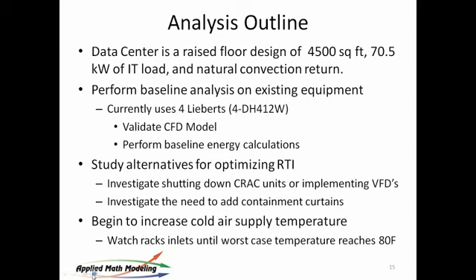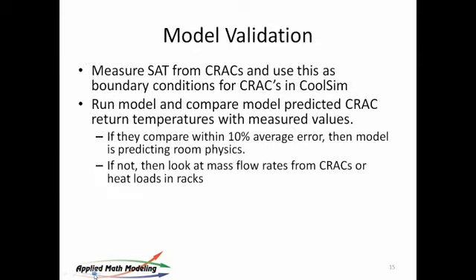In reality, the actual heat load on the servers is often quite a bit less than the nameplate ratings, and so that's why measurements are important if they can be made. Yes, very good point. Oftentimes, even in the IT world, they overspec, right? The IT manufacturer will tell you, well, that's a 2 kW box, and you put it in and you find it's reading 1.2 or something. So everybody worst cases the situation, and as a result, the optimization, the efficiency of the energy in the room is terrible because it's way off its design curve.